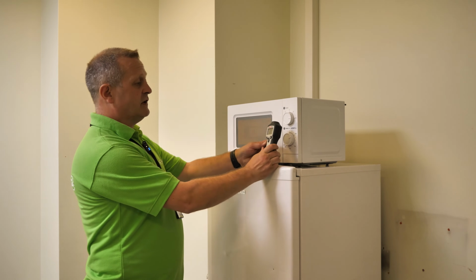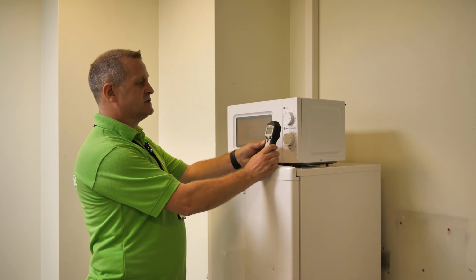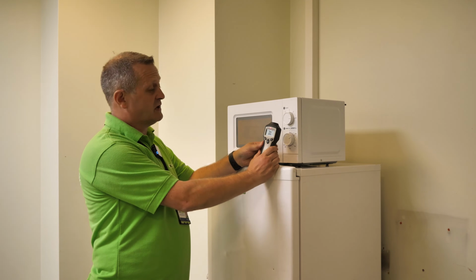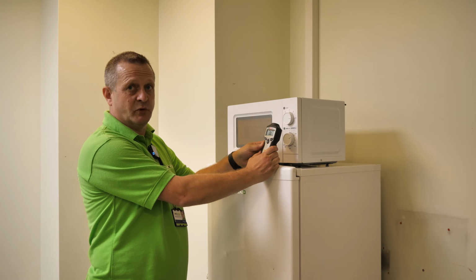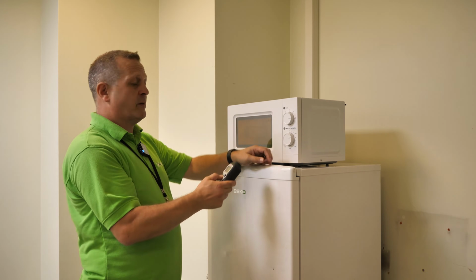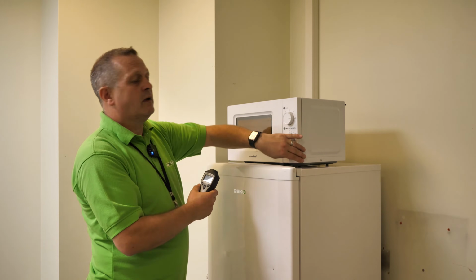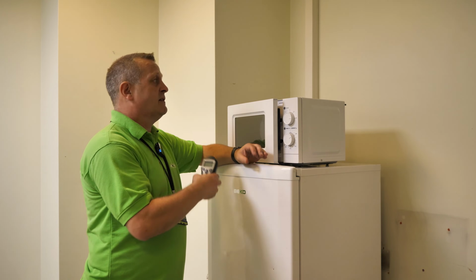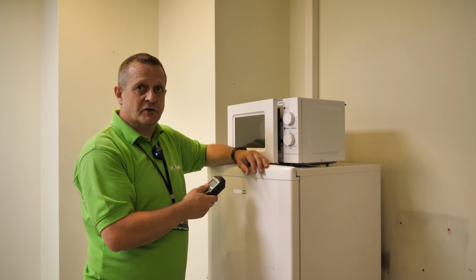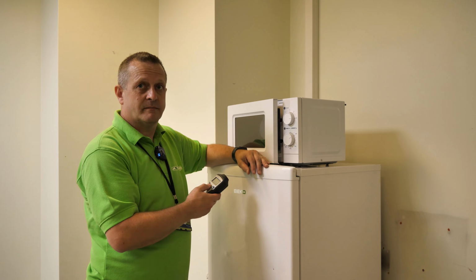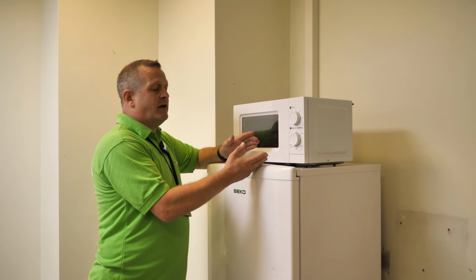And that's actually indicating that this is a failed item. It's indicating that it's well over the acceptable limits. So although it passed its class 1 appliance test, the appliance itself has failed because of the microwave emissions. So that is clearly a failure.